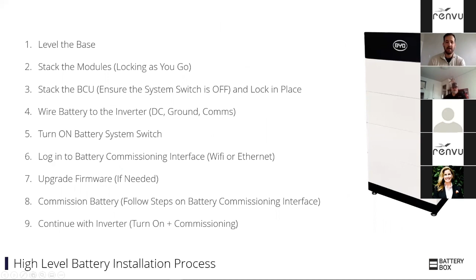So diving a little bit into this process in detail. Again, installation locations, as mentioned, indoor and outdoor rated. If outdoor, not in direct sunlight and not in direct rainfall, so under an eave, protected. And then definitely don't put it next to an open flame. The battery itself relies on passive cooling, so it doesn't have a fan in there. As far as clearances around it, really the clearances are dictated by access to conduit and access to breakers. But of course you don't want to put it next to something that produces heat and will heat up the battery itself.